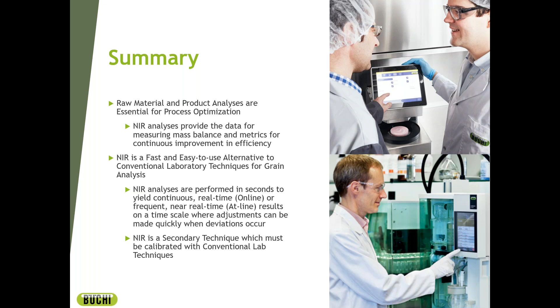Now here at BUCHI, our NIR calibration philosophy is to provide tools for the average user to create and maintain their own calibrations such that the calibration models are customized on the most relevant samples. AutoCal is a single keystroke operation that requires minimal training, and the customer, very important, owns their data and calibrations, and they do not need to pay a recurring fee.